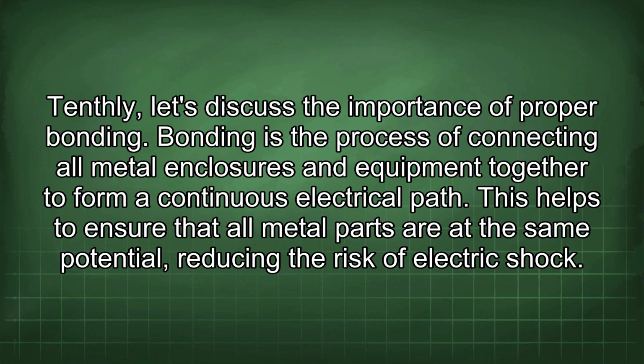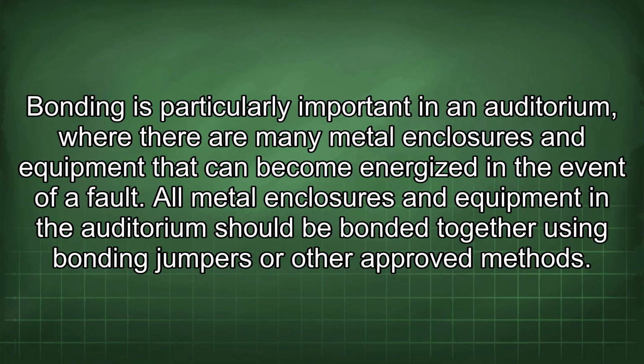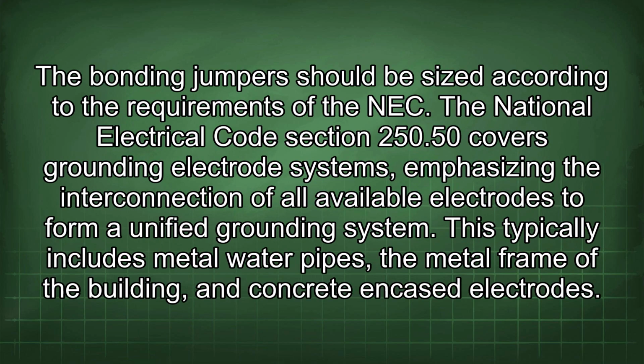Bonding is the process of connecting all metal enclosures and equipment together to form a continuous electrical path. This helps to ensure that all metal parts are at the same potential, reducing the risk of electric shock. Bonding is particularly important in an auditorium where there are many metal enclosures and equipment that can become energized in the event of a fault. All metal enclosures and equipment in the auditorium should be bonded together using bonding jumpers or other approved methods. The bonding jumpers should be sized according to the requirements of the NEC.